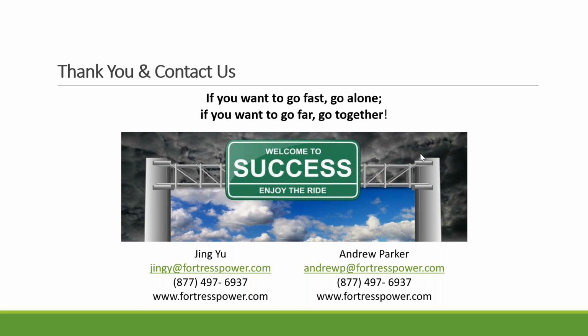But if you talk about demand curtailment, which is the 15-minute interval data where the utility is going to measure your loads and determine the highest number in the 30-day time period, that's when you need an energy management system that can measure your current load constantly and help you communicate with the grid and lower the demand charge. And we do have a third party that we work with that offers those energy management systems.